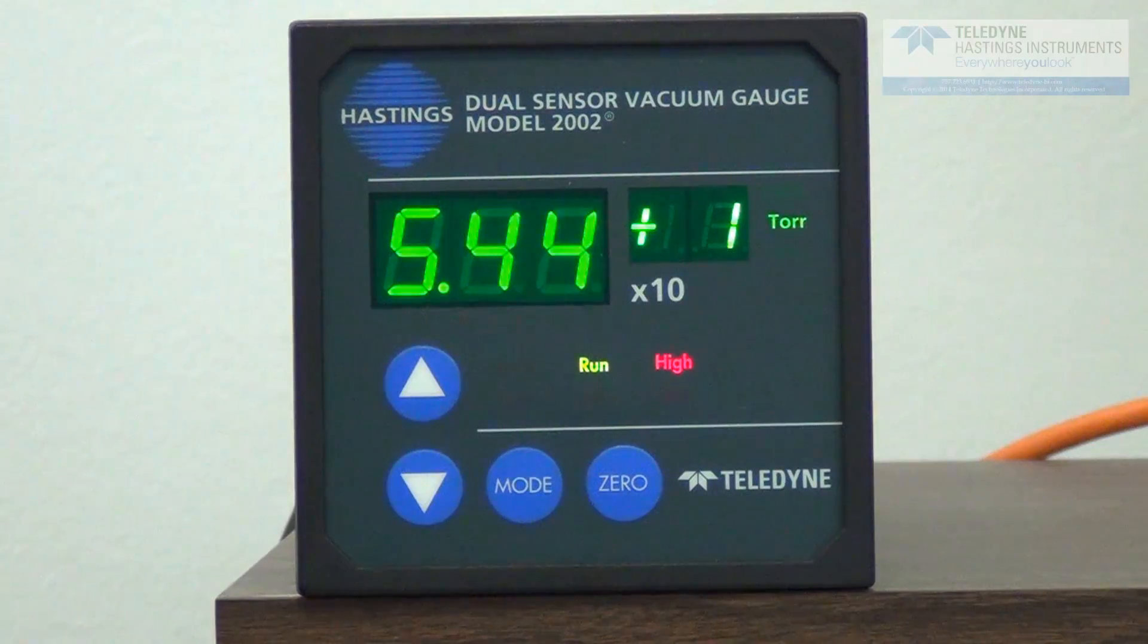So you see we're approaching 50 torr here, and we're going to get into the 32 torr region, the crossover region. And again, the microprocessor is always looking at both sensors. So now we're into the crossover region.